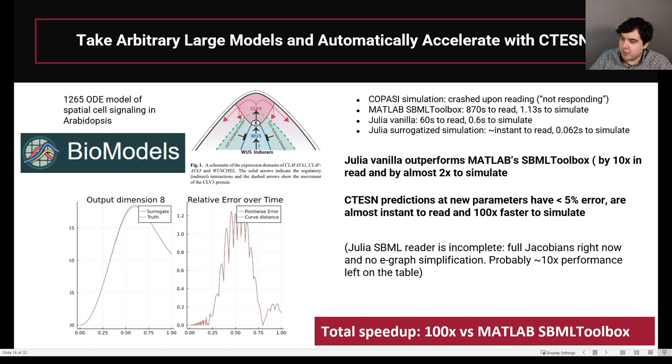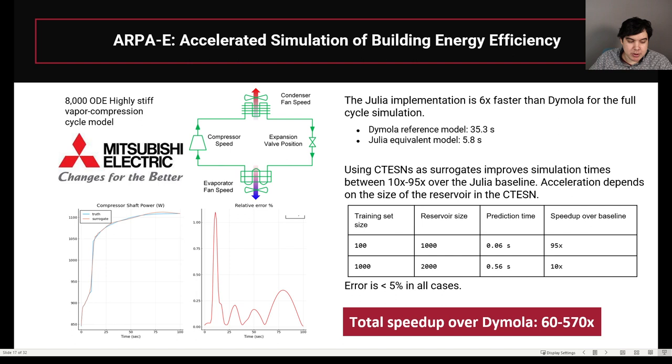On the HVAC models, what we showed was that you can get about a total speed-up over Dymola of about 60 to 570 times. Dymola is the leading compiler for the Modelica programming language. The Julia implementation of the HVAC model in the simulator itself is about six times faster because of the improved differential equation tools that I mentioned at the beginning. When you take the echo-state network and you train it, you're able to keep your error below 5% over the full time span. When predicting at new parameters, with this behavior at below 5% error, that's when you're able to see this 60 to 570 times speed-up. You can predict the behavior of the HVAC and the controllers basically faster than real time by using this trained continuous-time echo-state network.